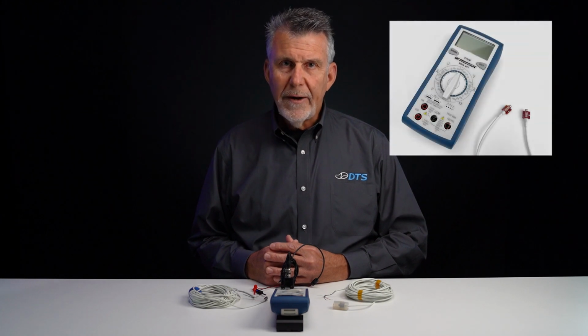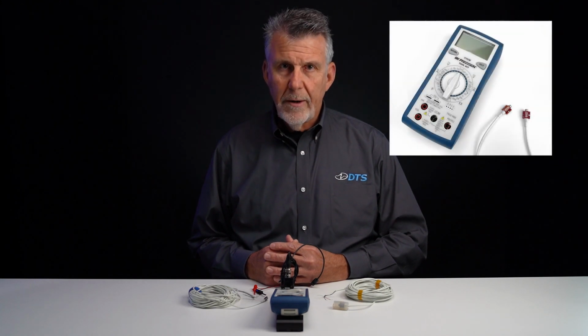What do you do if you can't make sensor diagnostic readings pass? You might feel like you've tried everything in terms of putting the correct settings into the software, but you still get a diagnostic failure. Well, when this happens, experience has shown that the vast majority of failures like this are caused by a sensor problem and not the DAS. Today we're going to figure out how to use a multimeter to check a sensor on the bench.